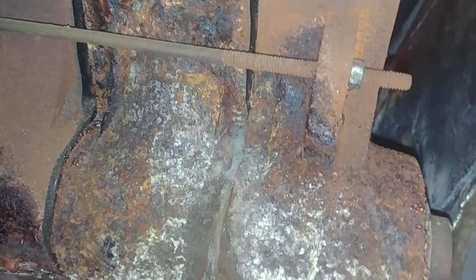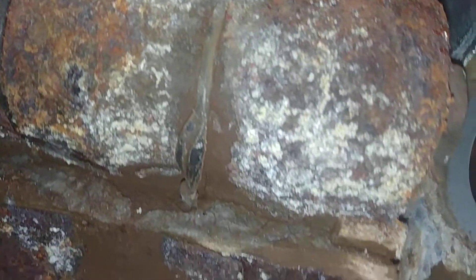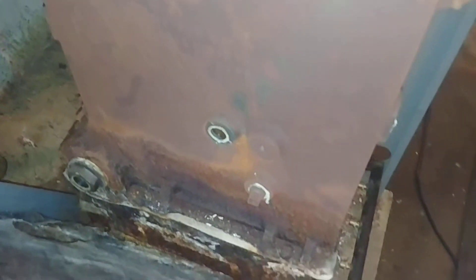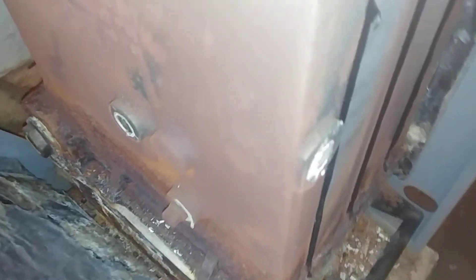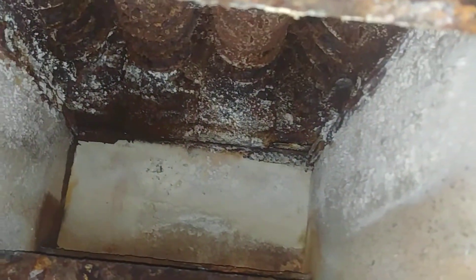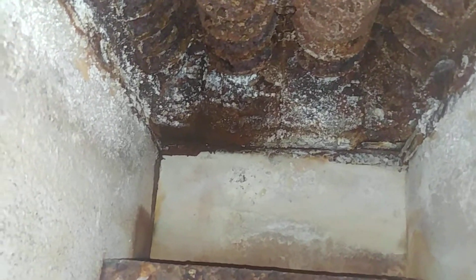Where it appears to have failed is the bottom section seal — at least one or two. You can see it really rusted out in the firebox there. There's the cast iron tag and what looks like the manufacturing date. We've removed the burner tubes and you can see inside the firebox — it is pretty crusty.